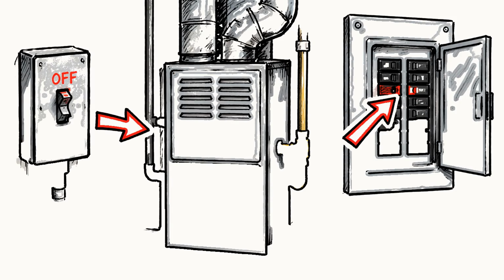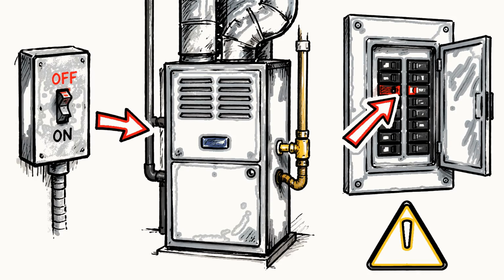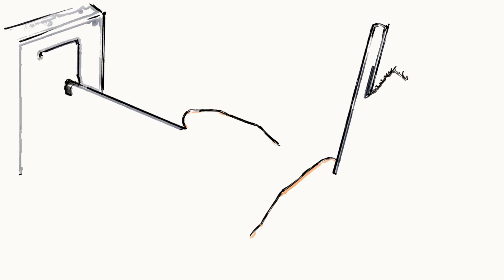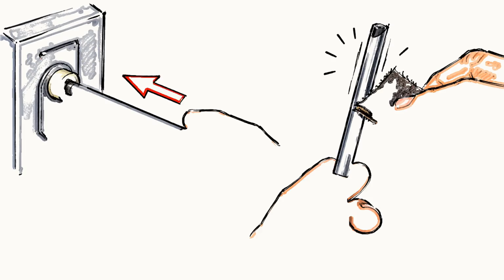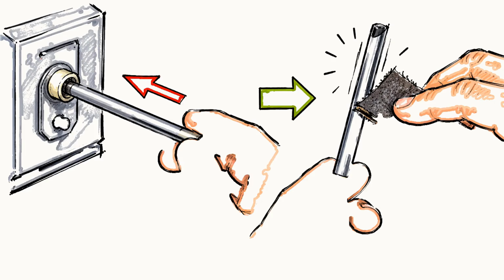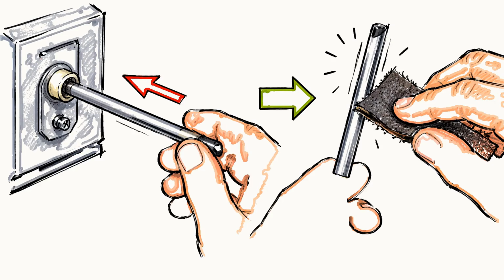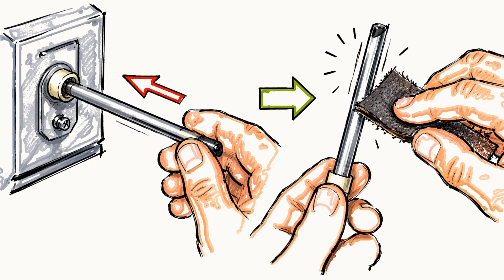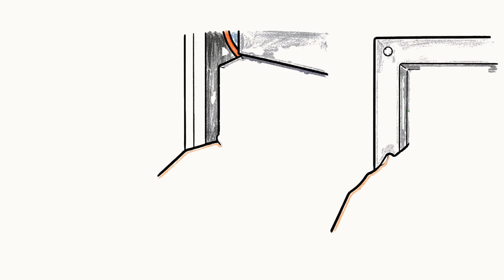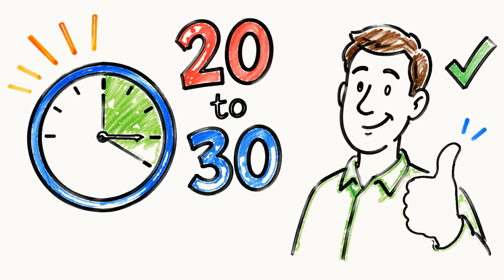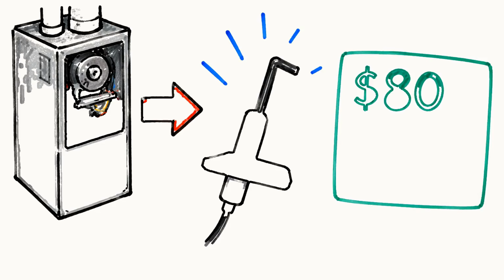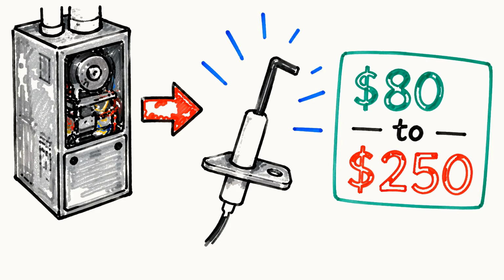Cut the power to the furnace at the switch on the unit or the breaker, because you are working near gas and electrical, and that step is not optional. Then pull the flame sensor rod out, usually held by one small screw, and gently scuff the metal with fine emery cloth or light steel wool until it is clean, dull metal again. Wipe it off, put it back, and restore power. The whole job takes 20 to 30 minutes and a beginner can do it. If cleaning it does not hold, a new sensor runs about $80 to $250 installed.